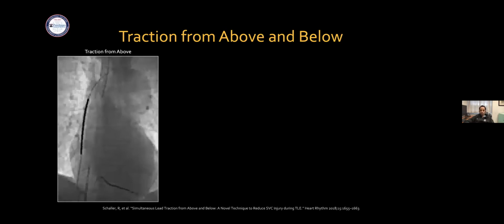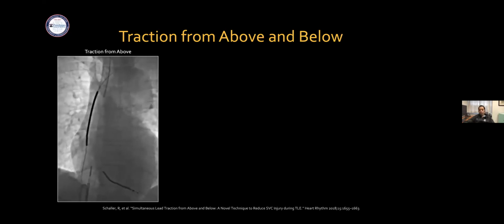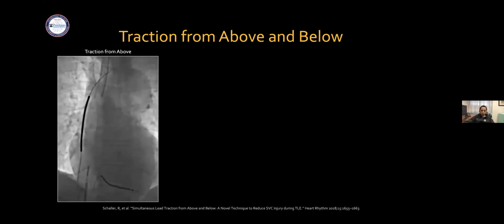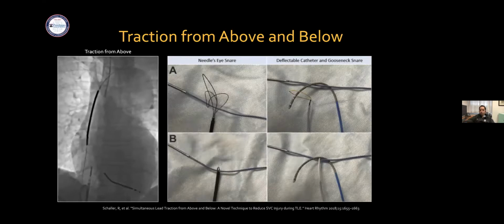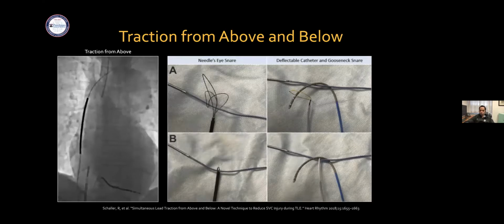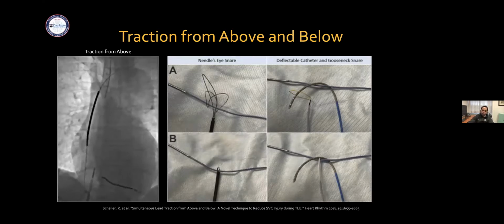So this is the technique that we use in situations where we think that the lead is attached to the SVC. If you pull the lead from above in a typical situation, what happens to the lead is that it pulls upward and to the right of the screen, slightly away from the SVC. But it doesn't separate very much. And if the lead is adhered to the SVC, it kind of pulls the SVC with it, or at least that's what we think is happening. So what we do in this situation is we snare the lead from below, either with a needle's eye snare or a deflectable catheter with the gooseneck snare, as I showed you before, and we utilize simultaneous countertraction.